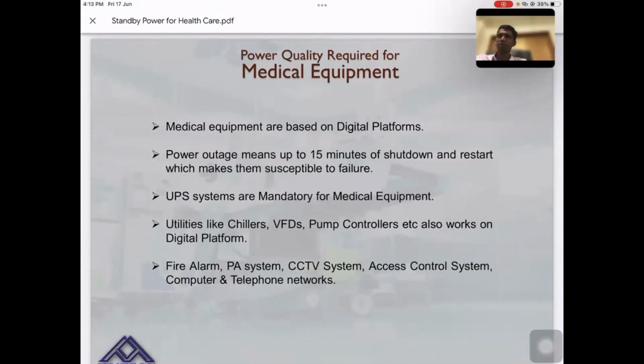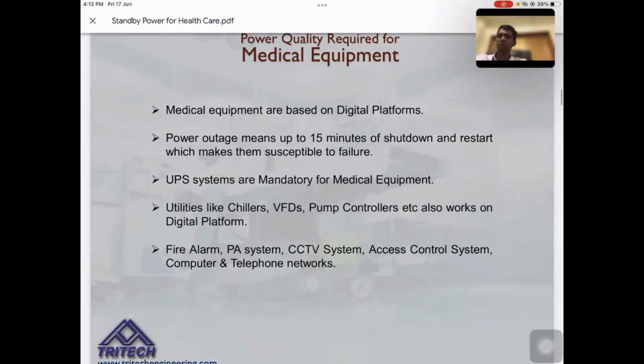And if you look at the power requirements of the medical equipment, you can clearly see that every modern medical equipment is based on a digital platform. Digital platform means everything has a processor and a system that is supporting the processor. So in the case of medical equipment working on a digital platform, a power outage means restarts will take somewhere around 15 minutes at least. Maybe it can be between 5 minutes to 15 minutes. Every time it is starting off, it is getting more and more susceptible to failure. So a power outage is actually a very damaging thing for medical equipment.